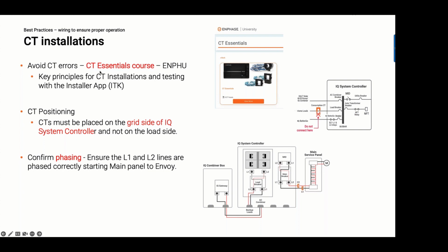The next common CT installation error is related to the placement of consumption CTs in the system. Installers place the CT on the load side of the system controller, wanting to measure consumption of the backup loads in the system. This is actually the wrong place to install the consumption CTs, as the system needs to meter all loads and consumption to properly control the system. Consumption CTs therefore must be installed on the line or grid side of the system controller for proper operation and system metering.